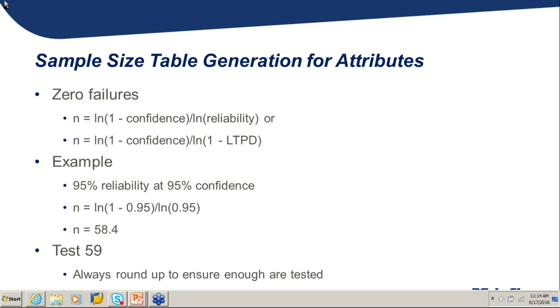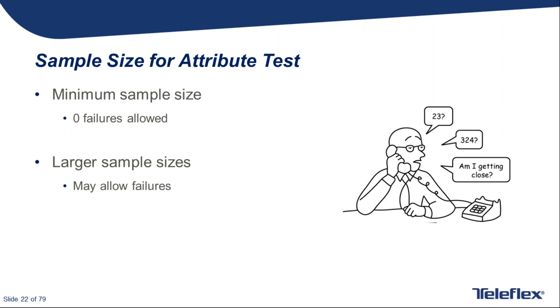Confidence and reliability requirements may be demonstrated for any number of failures, provided the sample size is large enough. Calculations for non-zero failure numbers may be more complicated, but are established and straightforward for statisticians to use to create tables for everyone's use. There are many options for sample size calculators for attributes on the internet. So one thing to keep in mind, though, if cost is a consideration, 0 failures is the way to go. You just have no slack, and if you do get a failure in testing, then it really needs to be explained well, or all the testing needs to be redone.